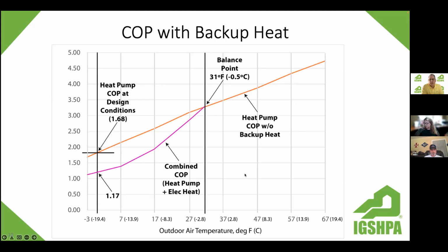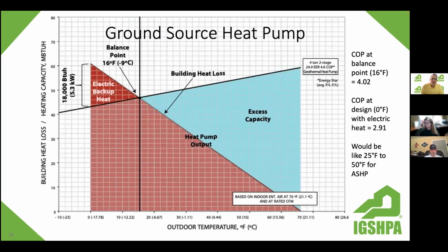Now let's bring in the geothermal heat pump and see what that does to our electric requirements. I did use the same graph. Obviously, geothermal doesn't care about the outside temperature, but in order to use this graph, I correlated the entering water temperature with the outside air based upon what we would typically see. So this line right here is the geothermal heat pump heating capacity as it gets colder outside. Of course, when it gets colder outside, the heat pump runs longer, so the loop gets colder. So we do have a lower capacity as it gets colder outside, all the way down to this design temperature here. So that's still our heat loss, this line. This is the heat pump capacity.